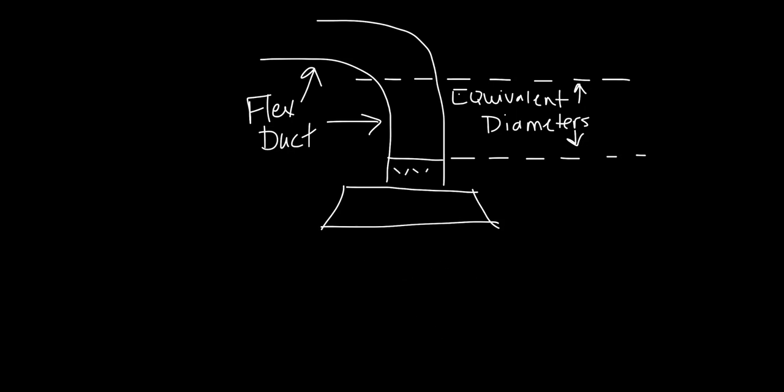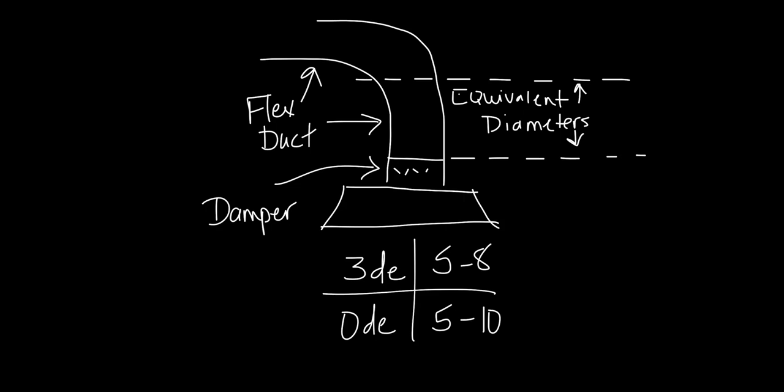The fourth case is exactly like the third case, only an opposed blade damper was added to the installation. At 3 equivalent diameters, it was found that the damper was responsible for adding between 5 and 8 NC to the baseline sound data. When zero equivalent diameters were tested, the sound add was between 5 and 10 NC. It is interesting that in both these cases, the low end of the sound data is the same and only a small difference at the high end.